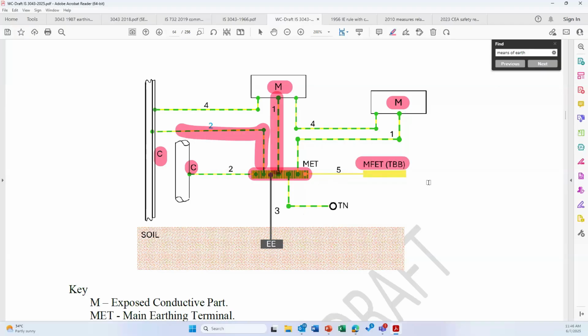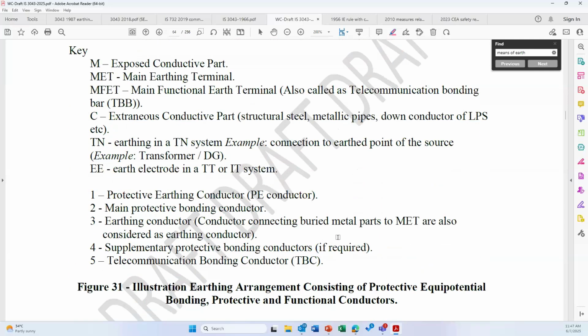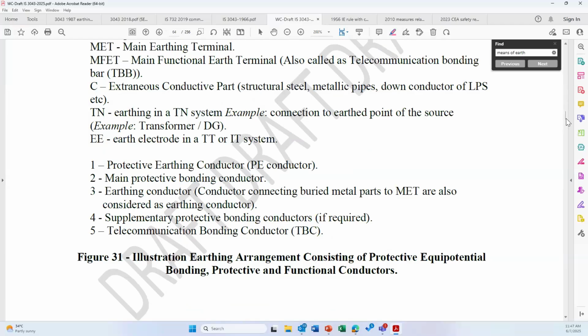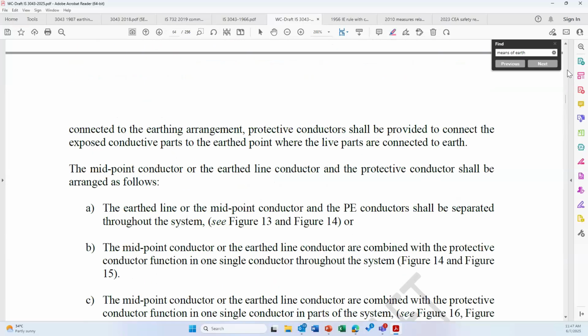Then you have the functional earthing, meaning the earthing of your electronic installations. You have a functional earth bus bar, and you should connect the MET and the functional earth bus bar. In case of a TN system, the means of earthing is the neutral of the source. In case of a TT system, the means of earthing is an earth electrode. All these explanations are being given in this particular clause.